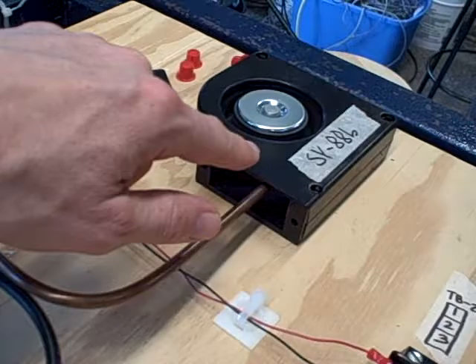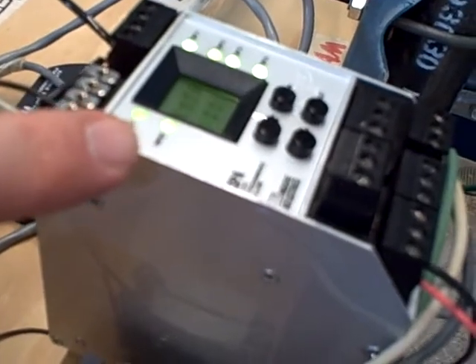The fan itself acts as a generator, so we can use the generator's voltage to measure its own speed. What we're doing here is we've added another layer of controls to it. This is a high-speed shutdown.